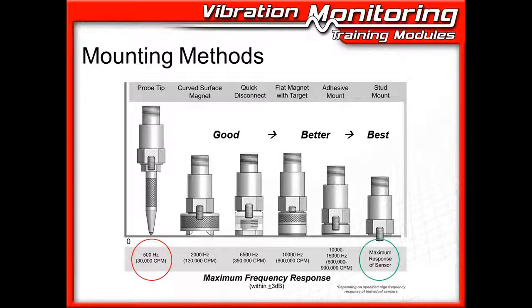I've actually got an example of why you only get 2,000 hertz there, and it's just a good look at what happens when you put something between the sensor and the machine. This is a quick connect. Probably has a much better application when used with a triaxial sensor, but if you're doing rapid roll changes or something, this is a good mounting method for rapid roll change, because you don't have to mess with the wiring. You just do the quick connect, drop it. When the new roll comes in, you hit it with a new quick connect, and you're connected again. You don't mess with the wiring at all.